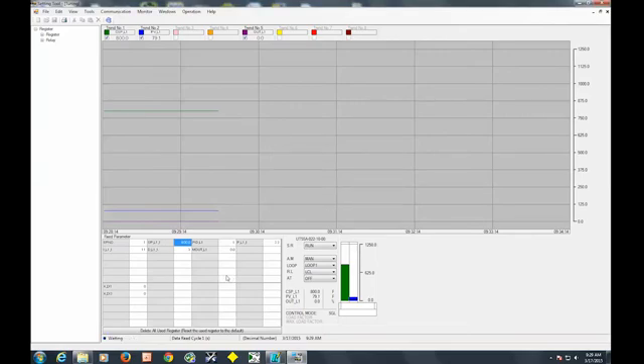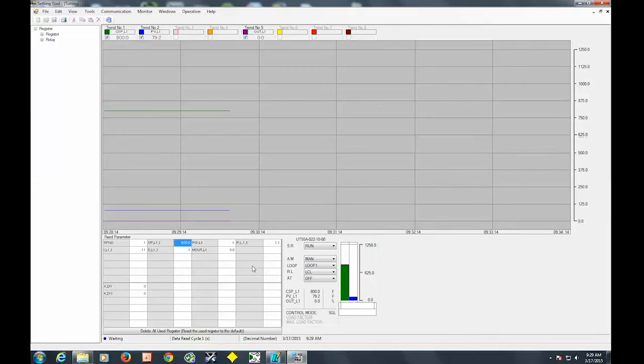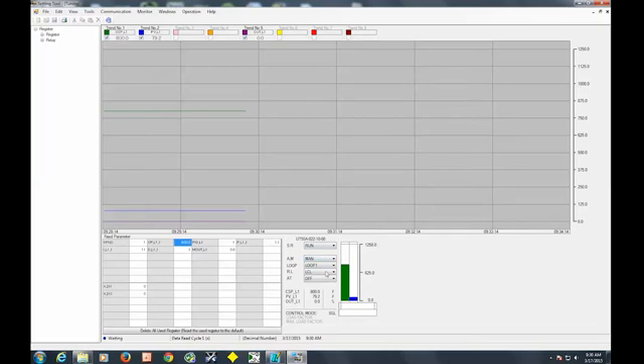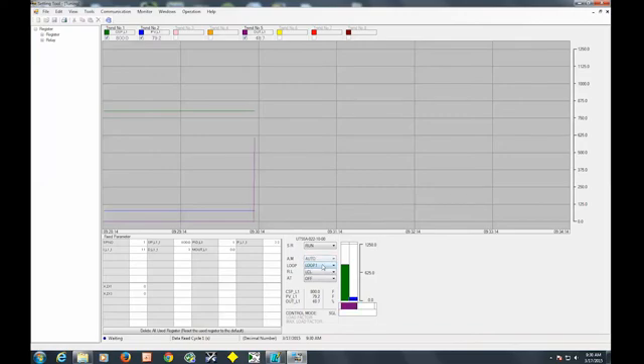To do auto-tune, the controller has to be in automatic. On the controller itself, there's a red LED in the bottom left-hand corner that needs to be off when you're doing auto-tune, signifying that you're in automatic. So to do that from the software, just go to the AM or auto-manual section, click and change it to auto. And you should see the red light go out on the controller.